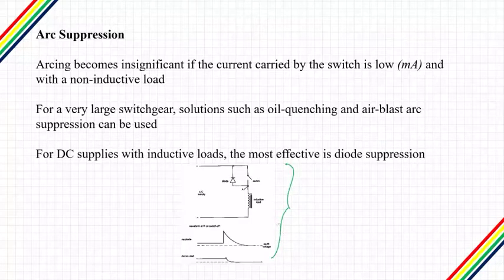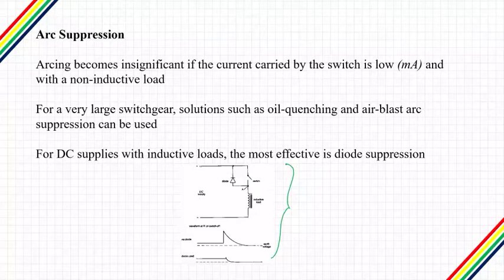The sudden drop of current through the inductive load will induce a voltage that is always in the reverse direction to the applied voltage across the switch, as described by Faraday's law of electromagnetic induction. By using a diode connected so as to conduct for this polarity of voltage — the diode is on reverse bias with respect to the DC supply, but it is conductive with the polarity of voltage that the inductive load will be inducing — so it will conduct current.